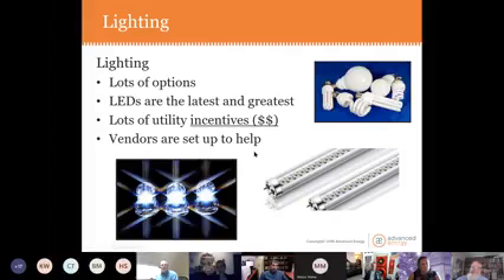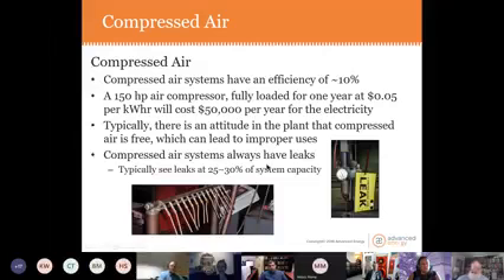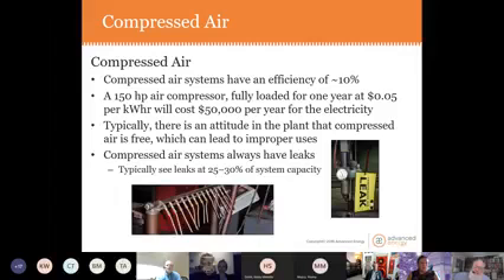They're way more efficient than, like, a 400-watt metal halide overhead light in a factory, which can be replaced with something on the order of a couple hundred watts or even less, a third or a fourth of the wattage to get the equal lighting. Compressed air. We could do a whole week's study on compressed air. Compressed air is the most inefficient energy source or utility in your plant. Typically, from the electricity to the compressor motor until you actually get the compressed air out to where it's doing something in the plant, is about 10% efficiency. It's absolutely terrible, and it's expensive.